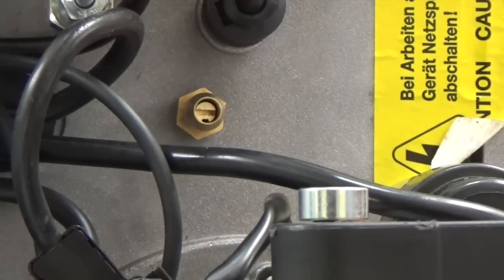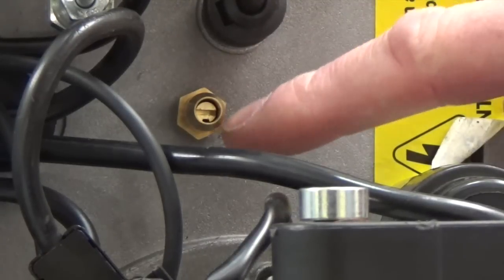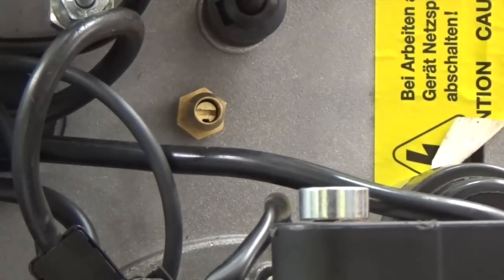The first step in the commissioning process is to ensure that the combustion chamber pressure is correctly set to 12.5 millibar, as this has an important effect on how the burner recirculates combustion gases back through the blast tube. The test point screw is released and a digital differential pressure gauge is used to record the pressure.